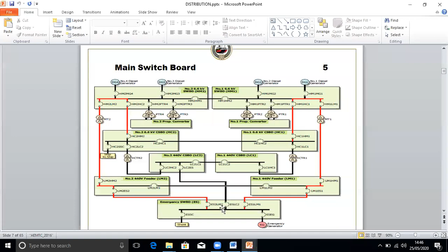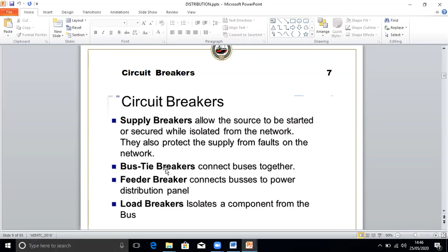So circuit breakers, supply breakers allow a source to be started and secured while isolated from the network. Bus tie breakers connect buses together. Feeder breaker means it connects buses to power distribution. Like if you have a steering gear motor from the main switchboard, it will come from the main bus bar to a feeder breaker. From the feeder breaker, it goes to your starter panel. Okay, so feeder breaker, bus tie breaker, supply breaker.